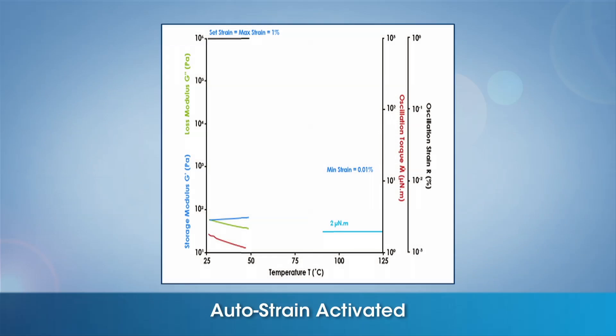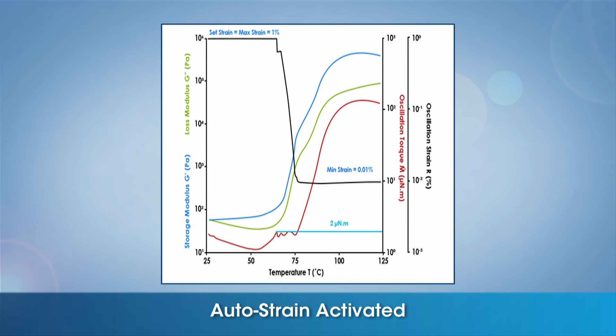This is to ensure that Auto Strain will take control at that point in order to reduce the strain while the material begins to cure, preventing shear damage to the developing sample network. The strain will continue to reduce at the rate specified from the strain adjust percentage to the set minimum value of 0.01%, in attempt to maintain the maximum set torque as shown.